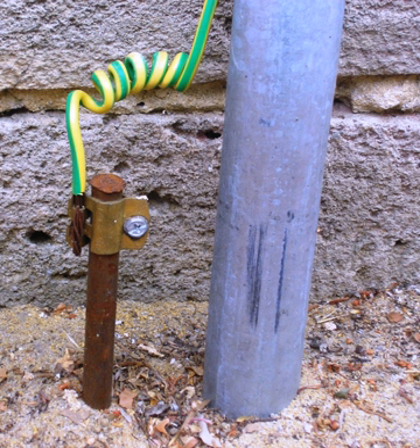When a system needs to be connected to the physical ground, earth, the equipment bonding conductor also becomes the equipment earthing conductor, see above. A grounding electrode conductor (GEC) is used to connect the system grounded neutral conductor or the equipment to a grounding electrode or a point on the grounding electrode system. This is called system grounding, and most electrical systems are required to be grounded.